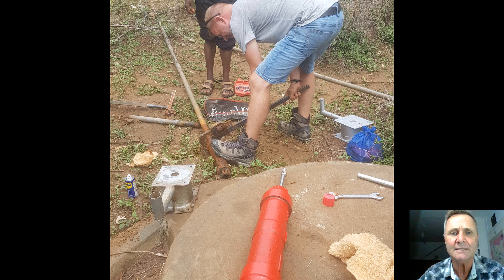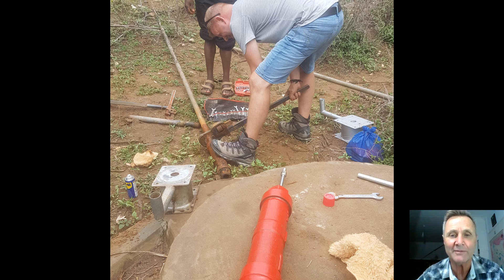This is us repairing a pump. Pumps are at the bottom of all the piping. We typically repair wells that are anywhere from 40 to 70 feet deep, and the pump is at the bottom. At least half the time the pump is the problem, or at least part of it. So we typically replace the pump once we pull it out, whether it's the problem or not, because it'll break sooner or later — probably sooner.